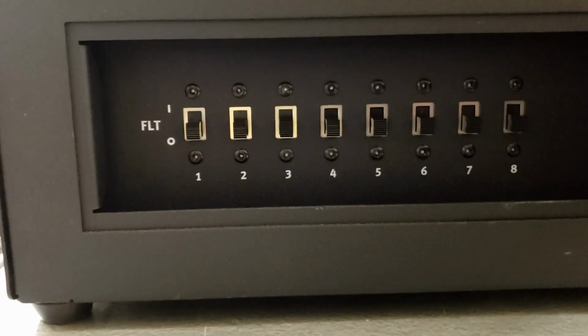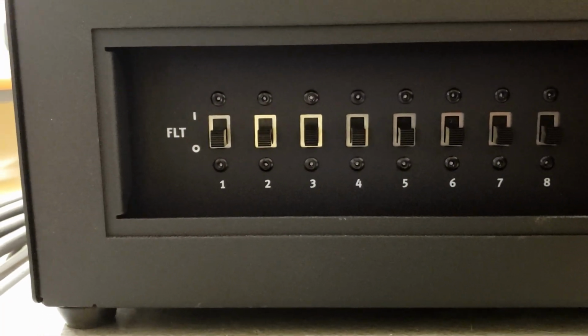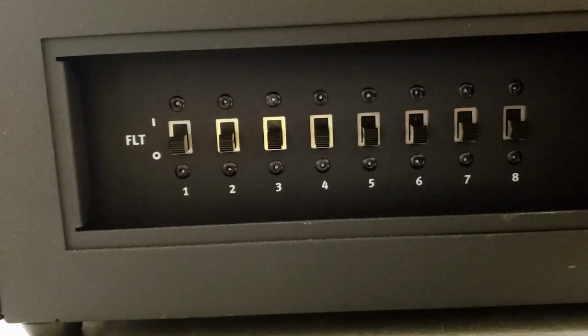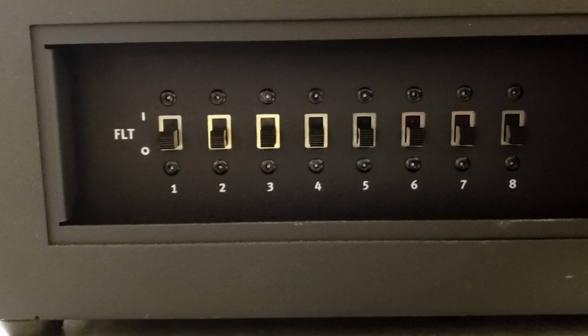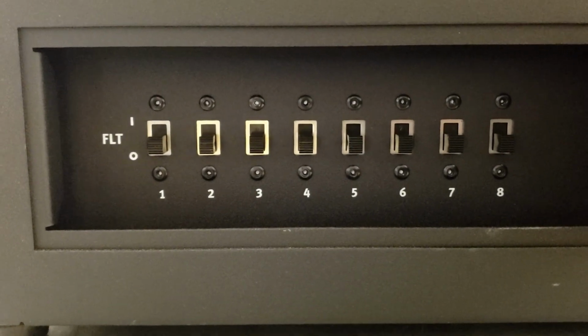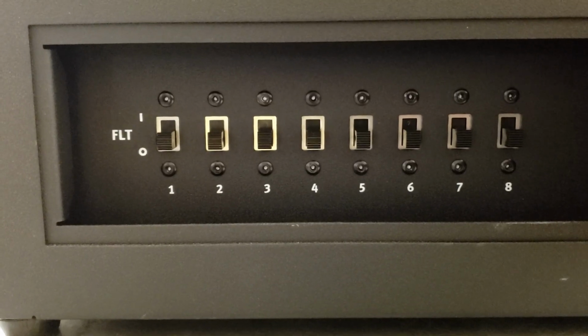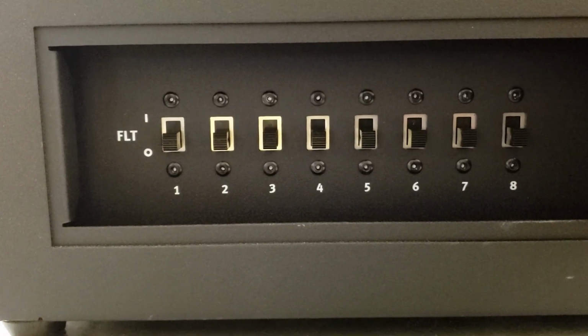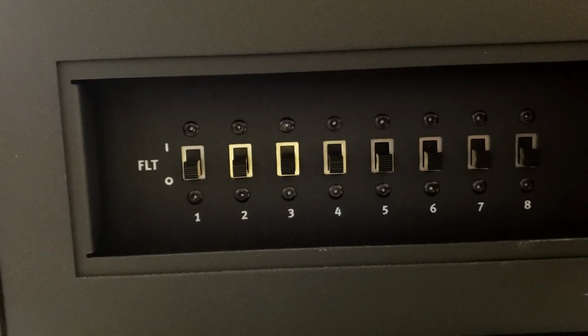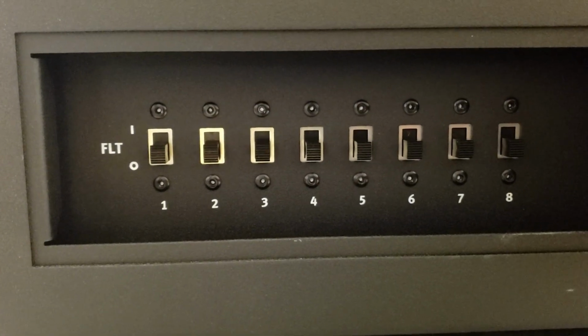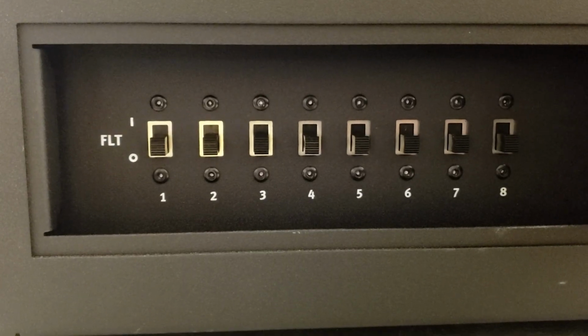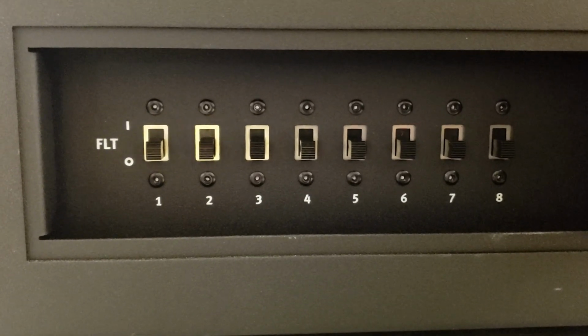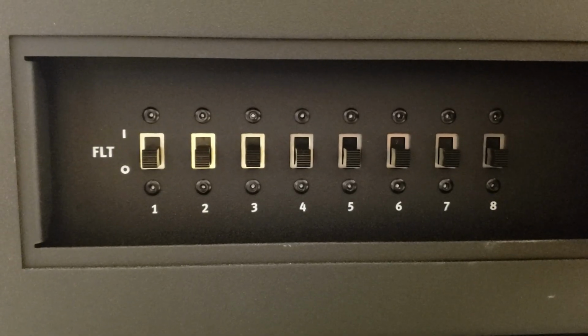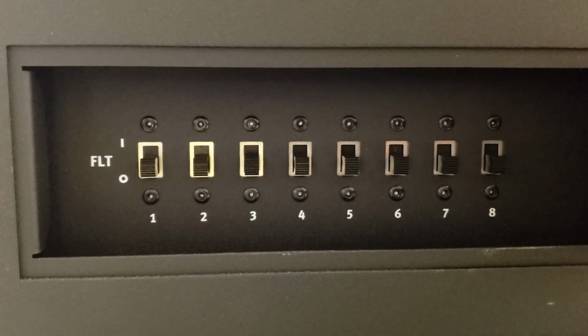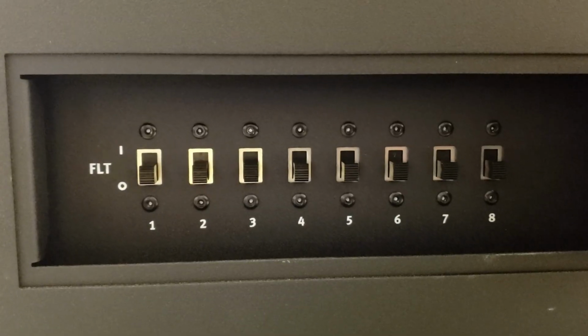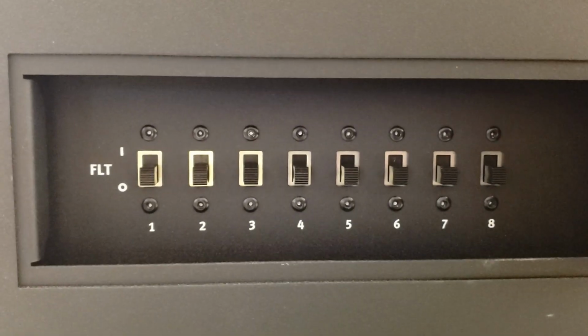There are 8 different faults, and on page 57 of the instructor manual: number 1 is an open primary on transformer number 1. Number 2 is an open secondary on transformer number 2. Number 3 is secondary of transformer 3 shorted to ground. Number 4 is line B shorted to ground. Number 5 is open primary on transformer number 4. Number 6 is open secondary on transformer number 5. Number 7 is secondary of transformer 6 shorted to ground. And number 8 is line C2 shorted to ground.